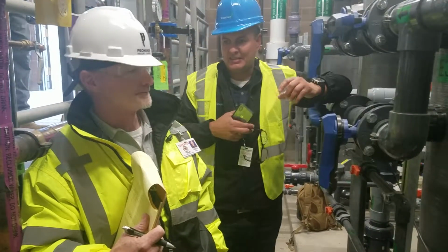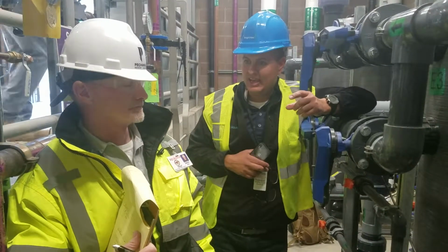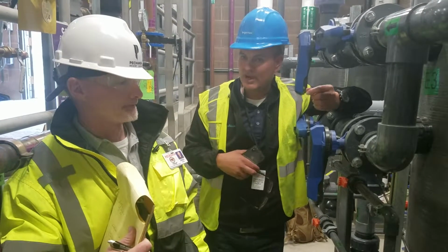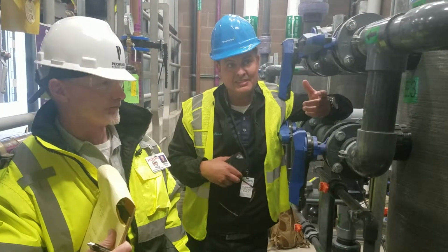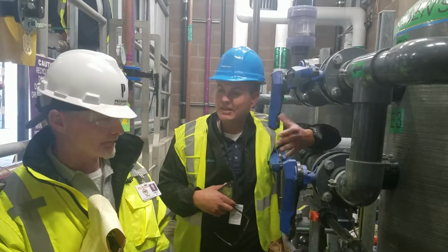Because what's happening is it's actually using that gel as an activator to read millivolts and pH, right? So if we're washing that stuff across there too fast, then we're going to end up washing that gel out of there prematurely, which creates inconsistencies in readings. So if we keep a consistent flow across that probe, then we get consistent readings.